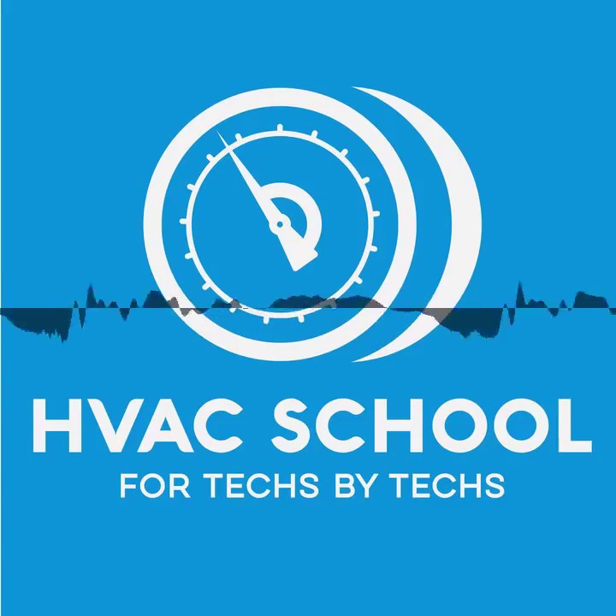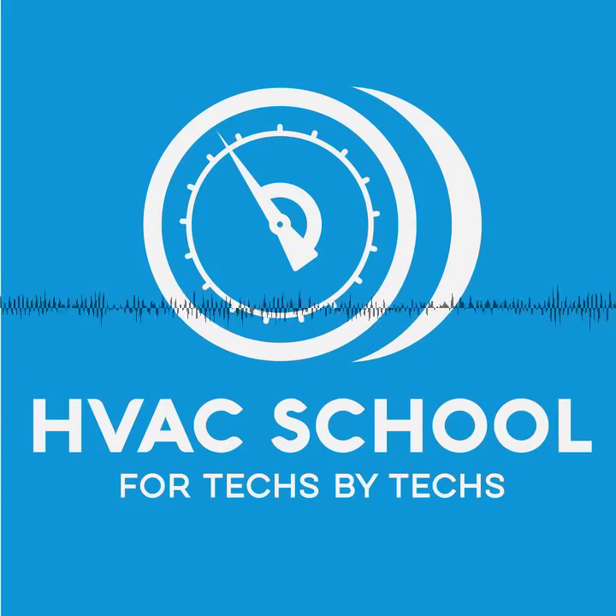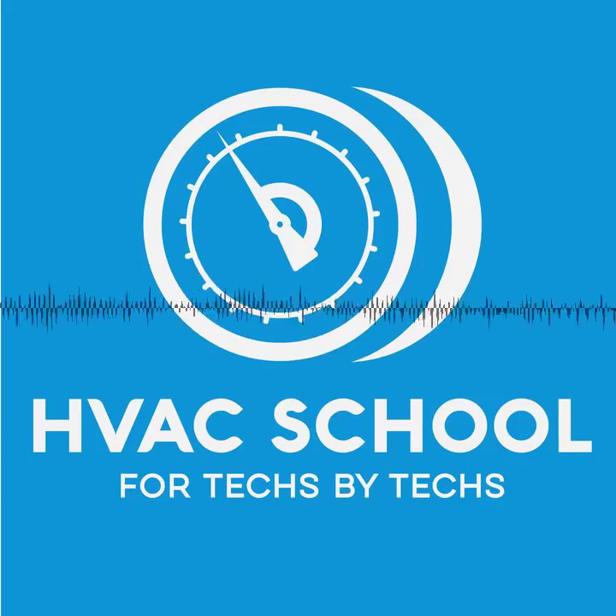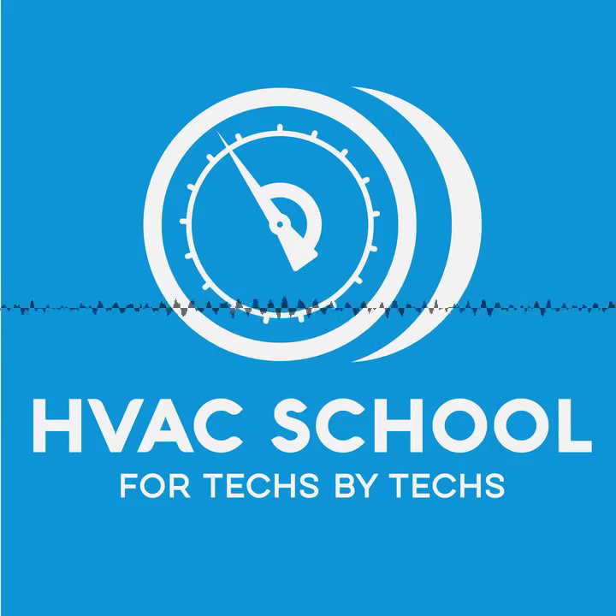One thing when you're measuring a Delta T, don't use an infrared thermometer. Don't use something that you're shooting with a laser. It's just not going to be accurate. They measure surface temperatures, not air temperatures. I see home inspectors do this a lot when they'll walk through the house and they'll shoot a return and they'll shoot a supply and they don't read a proper air temperature split that way. And also, when you do it inside the home, you're also taking into account any duct gains in between the system and the distribution point, in addition to the fact that you're reading the surface and not the air. So there's just all sorts of challenges there. Not to say that it's a completely useless measurement. It's just that you can't use the typical rules for Delta T that we talk about.